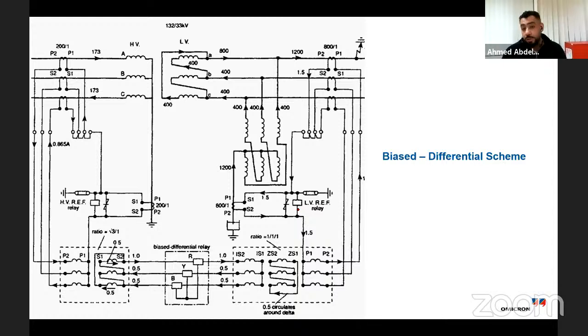This is a very old differential protection scheme. I worked on it in Saudi Arabia in the year 2008. Transformer, high voltage side, 132/33 kV. I have a high voltage side which is star, and you can see it is a grounded star transformer. And the other side is a delta, which is the low voltage side. What should I do?